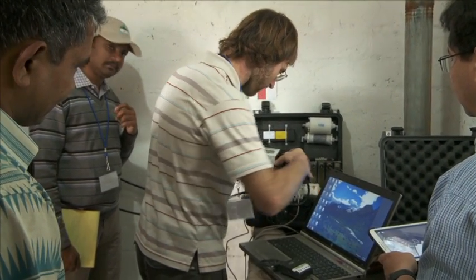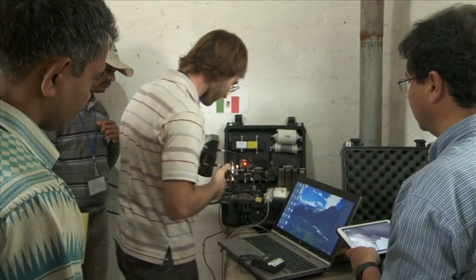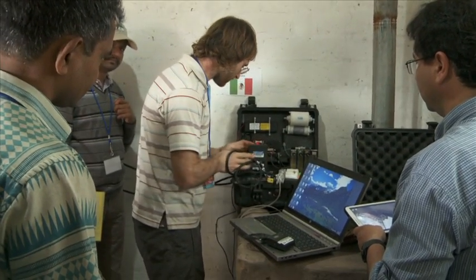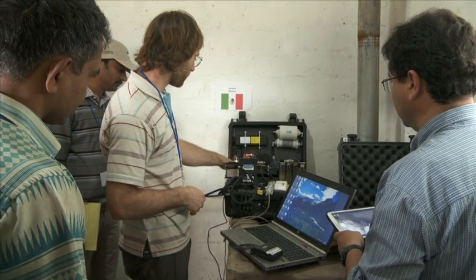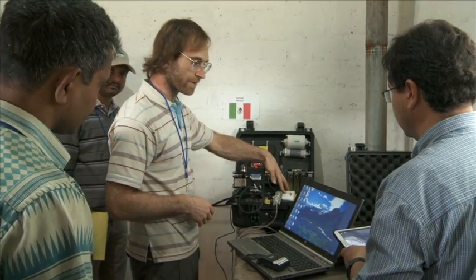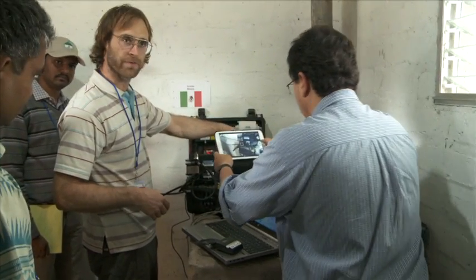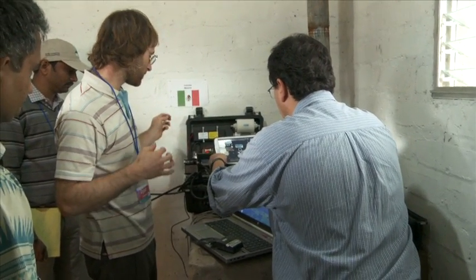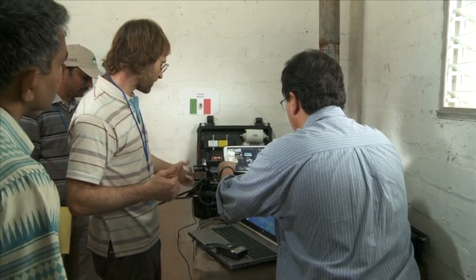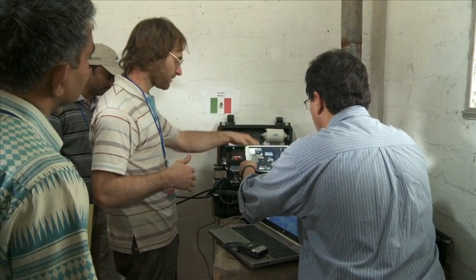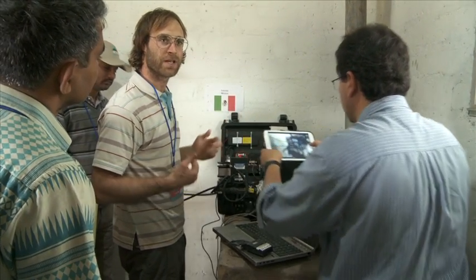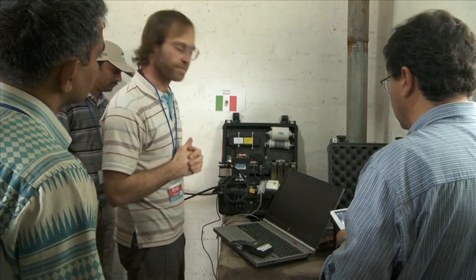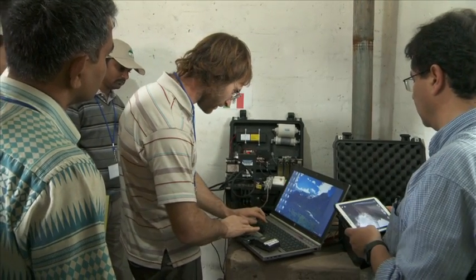How many different places do you have to check the flow? Like 4. We check the flow through the aethalometer. We check the flow through each filter, and then the bypass flow, and then we double check the flow in the inlet to make sure it adds up to all the other flows that we just checked. And if it doesn't, then we know there's a problem. I'm going to start logging the data.